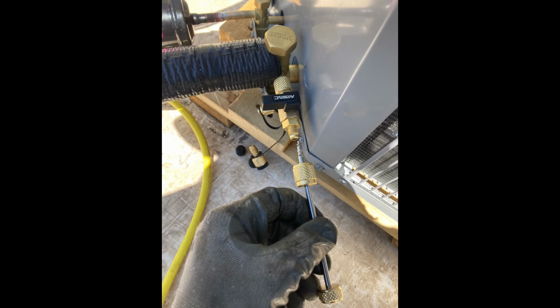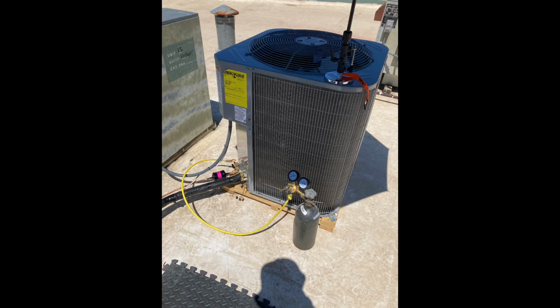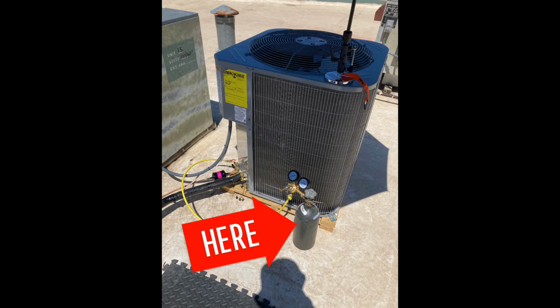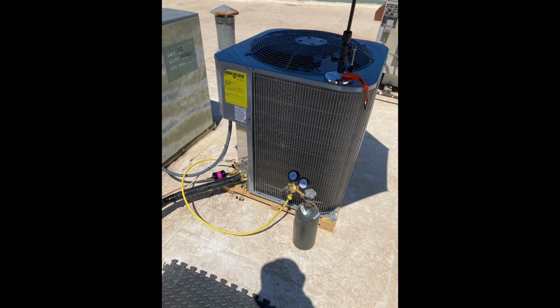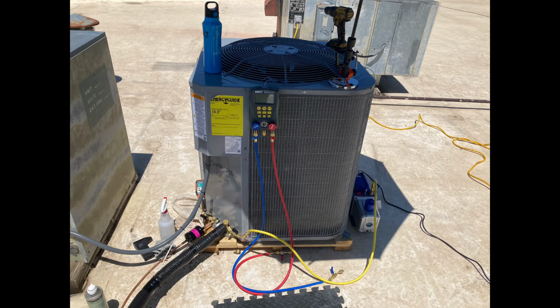So before I do that pressure test, I'm going to remove both valve cores from both service valves using the valve core puller tool that you see here. I'll reinstall the valve cores once we pass the pressure test, pull the vacuum, and release the refrigerant charge from the condenser. You can see I got my dry nitrogen hooked up to my regulator, hooked up to my line set. So basically you got to hold it for a certain amount of time and the needle shouldn't move on the gauge. So once we pass that test, it's also called a decay test.